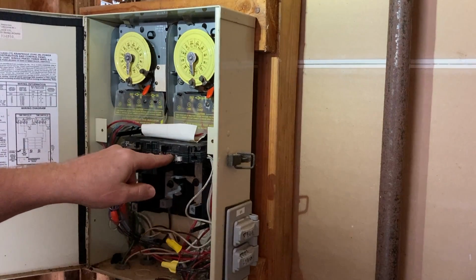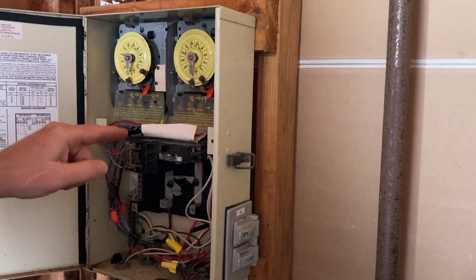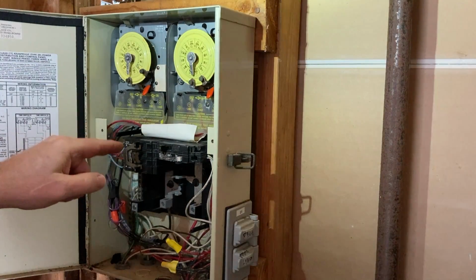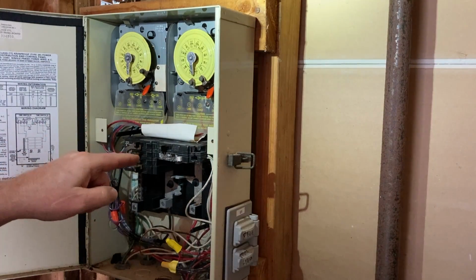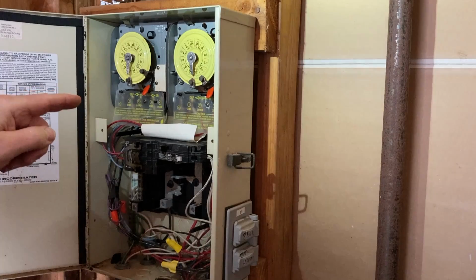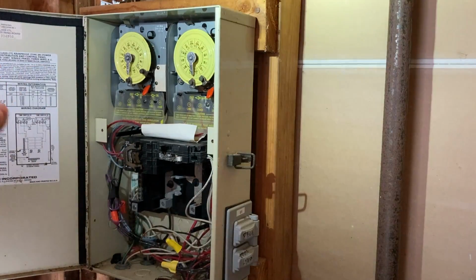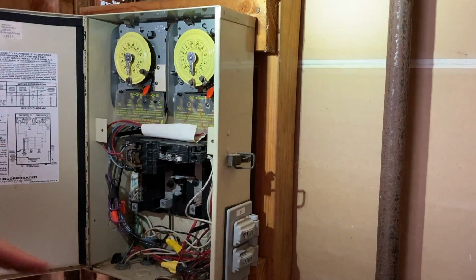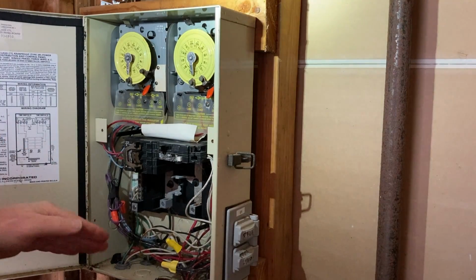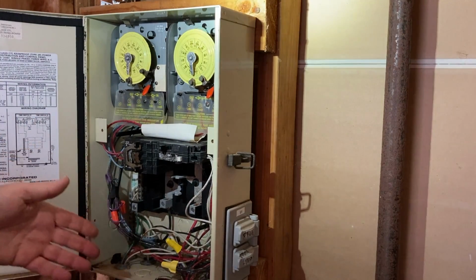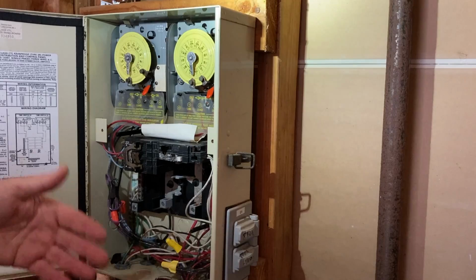I think that the spa, the hot tub, because it's a 110 volt 15 amp unit, should be on its own circuit by itself, because it practically uses the whole circuit. And in fact, since they had to wire a special plug for it, I'm surprised they didn't put in a 20 amp just to have a little headroom current wise, but they didn't.